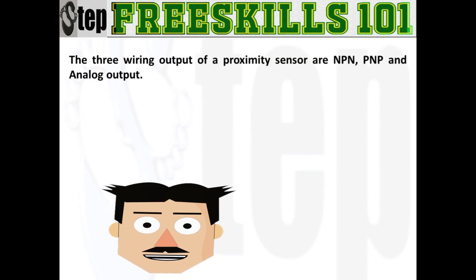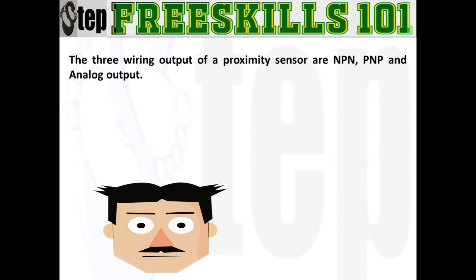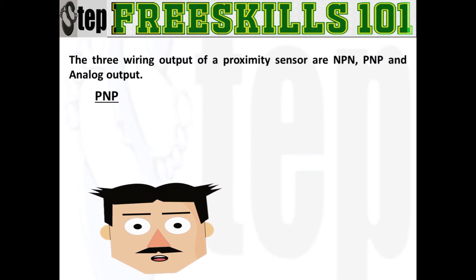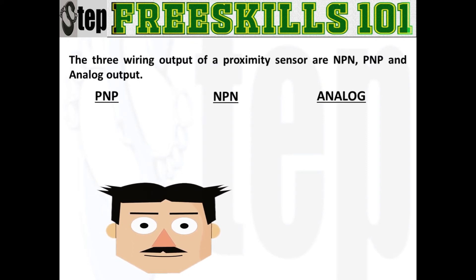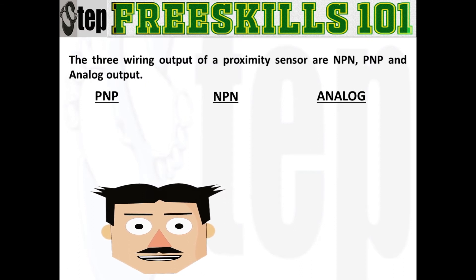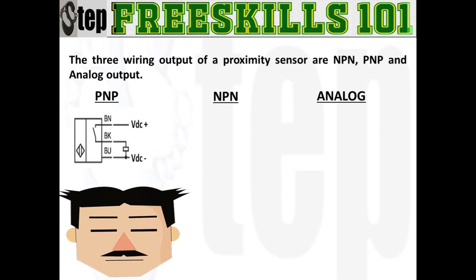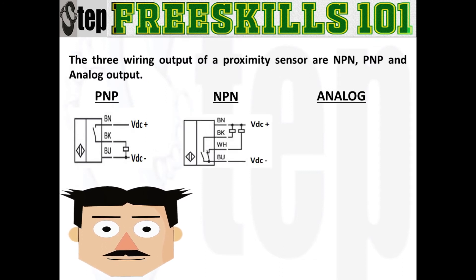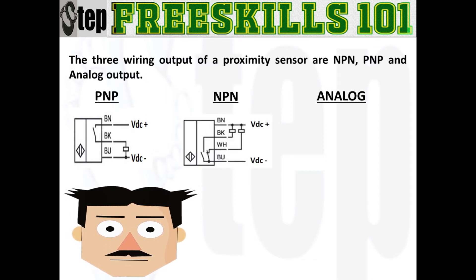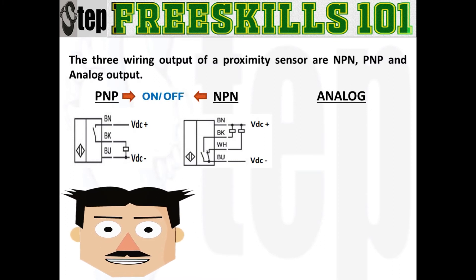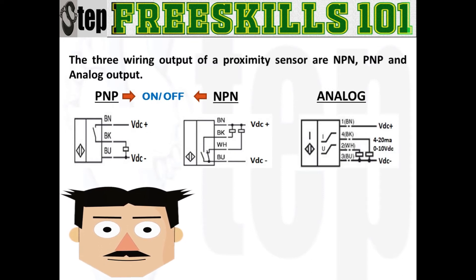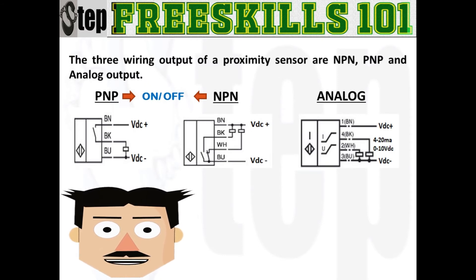Among the different technologies of proximity sensors, there are three types of wiring output: NPN, PNP, and analog output. Both NPN and PNP are on and off, therefore they are considered as digital input devices. And last, the analog output of 4 to 20 milliamps or 0 to 10 DC voltage.